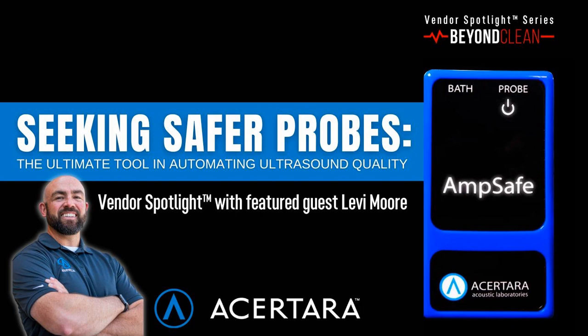So we've done full FDA 510K submissions, but a lot of what we do is focused specifically on the safety of the ultrasound itself. So making sure that you don't have focus where you don't mean to have a focus, or the total energy going in isn't too much at a single place at a single point in time. It's pretty embarrassing for everybody if you go in to get an ultrasound scan and you cook their liver instead, or you cook whatever it is that you are trying to image. So they're pretty careful about making sure that those values are proper.